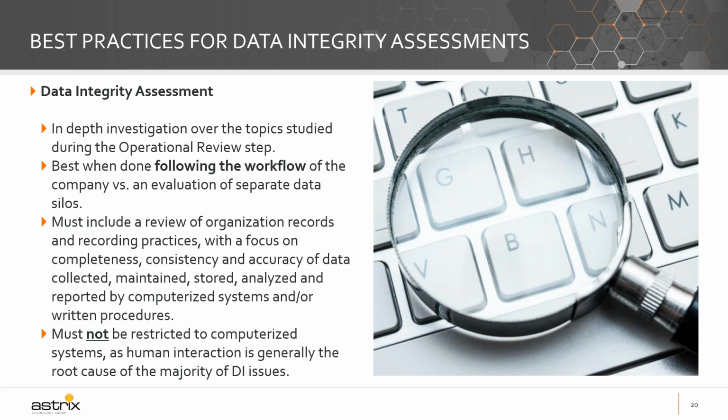If the data integrity issue occurred right before data goes into your ELN, and then you bring that information over, it is already tampered and you would not get that if you're only focused on the application instead of the entire workflow of data. So whenever you're doing an assessment, the best way to go is to look at the workflow of data and not exactly at one application or another.